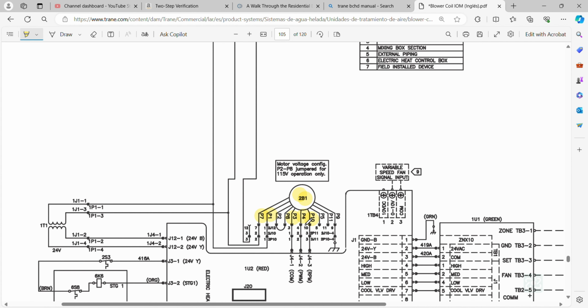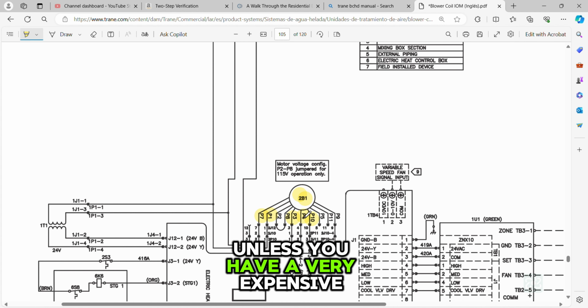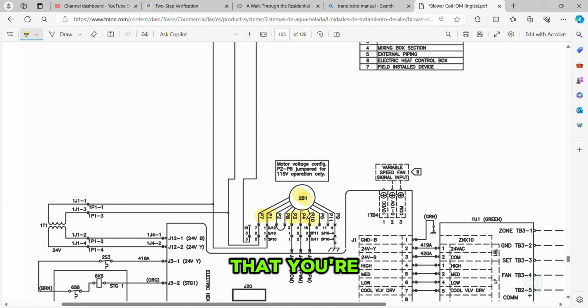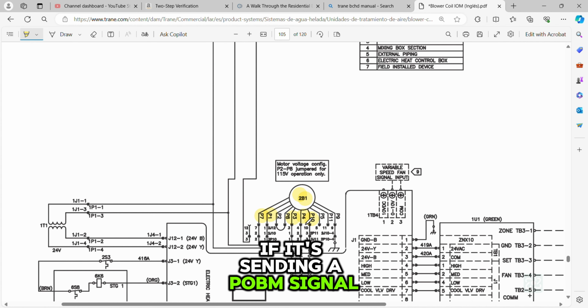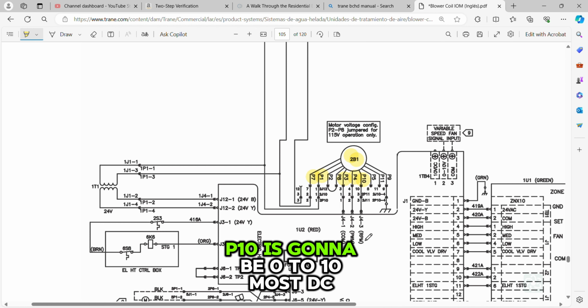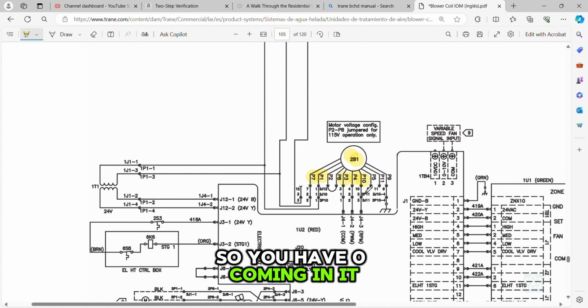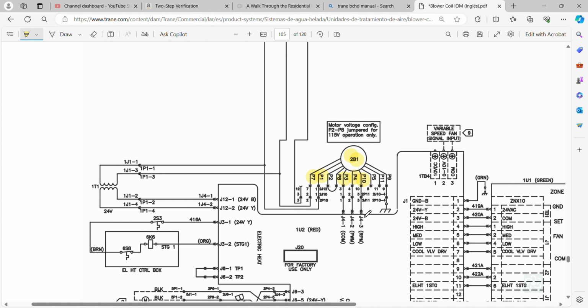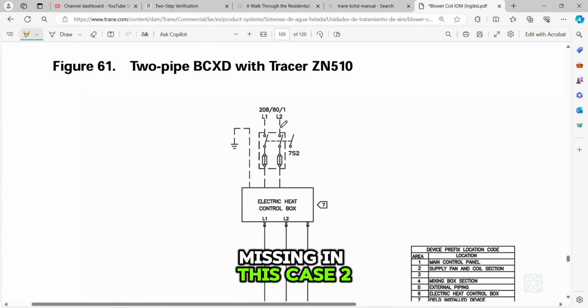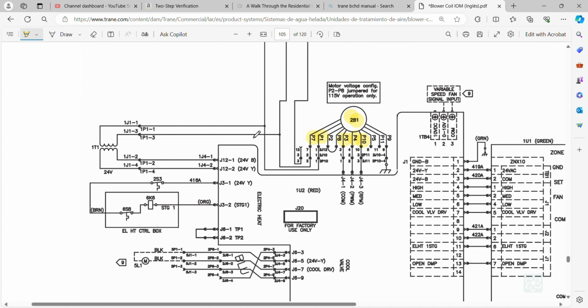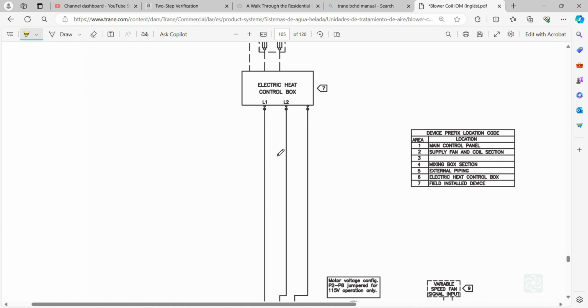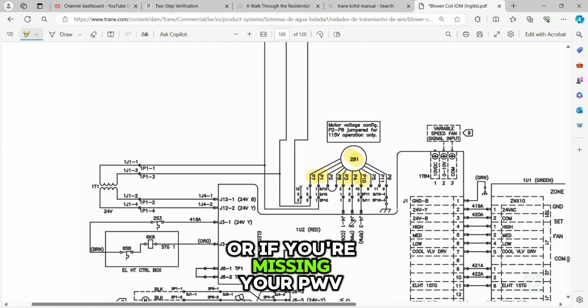P4 is going to be pulse width modulation, so unless you have a very expensive meter that can actually measure that, you're going to show basically erratic readings if it's sending a PWM signal. And P10 is going to be a 0 to 10 volts DC signal, so if you have 0 coming in at the P10 input, then you've got another problem besides the DC module or the motor itself. The same goes if you're missing, in this case, 208 volts from L1, L2 coming in at the motor or the harness on the penetration to the air handler, or if you're missing your PWM signal.